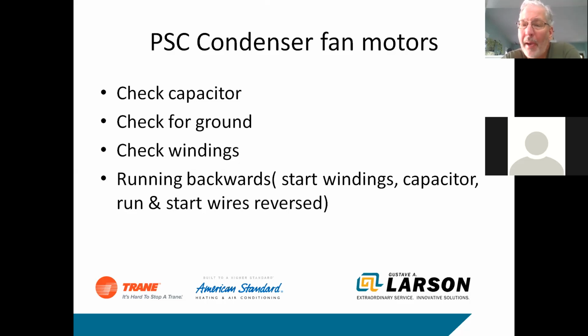If a fan's running backwards, and I get this call every now and again, it could be a couple things. It could be the start winding is burned out on the fan motor, and the run winding has the ability to turn in either direction at that point. Okay, so start windings are out. It could run backwards, it could run forward. It's kind of a hit and miss kind of thing.